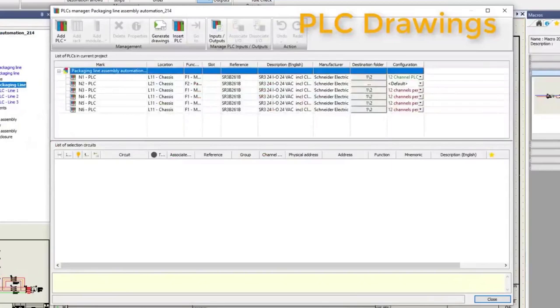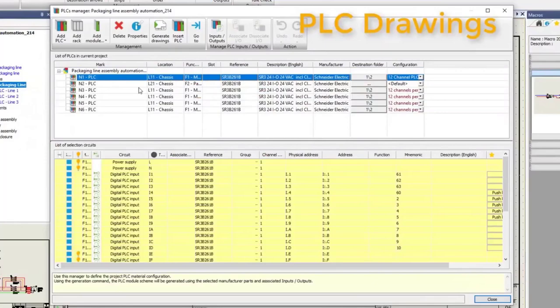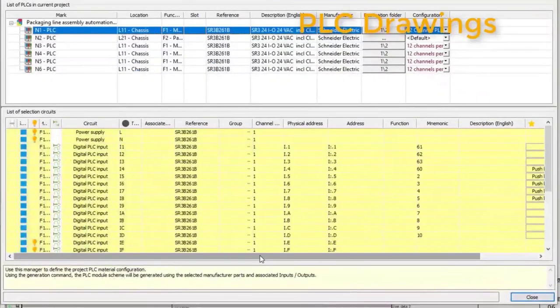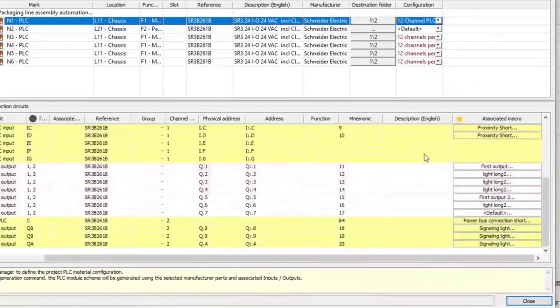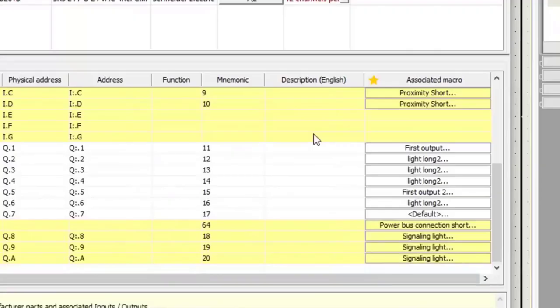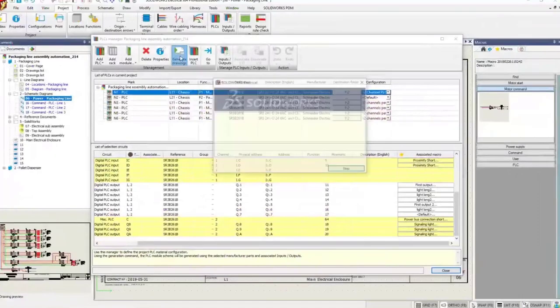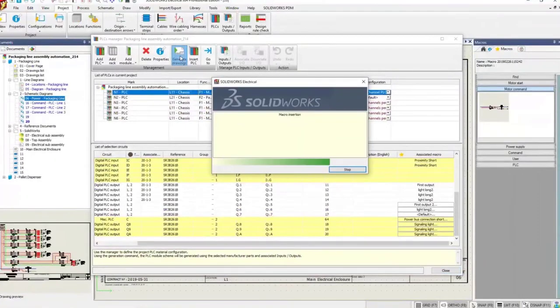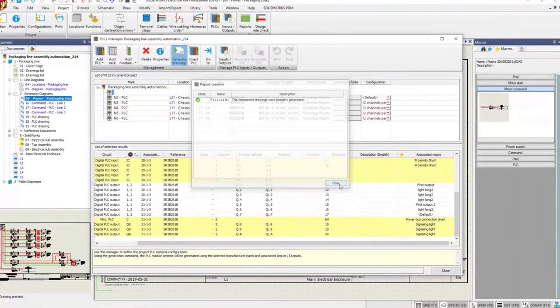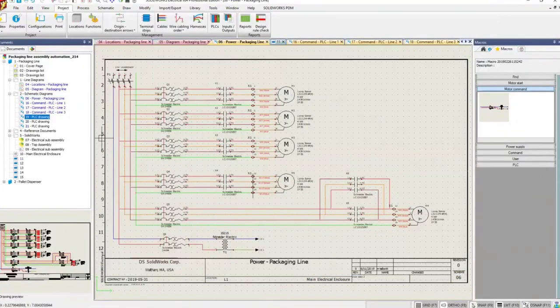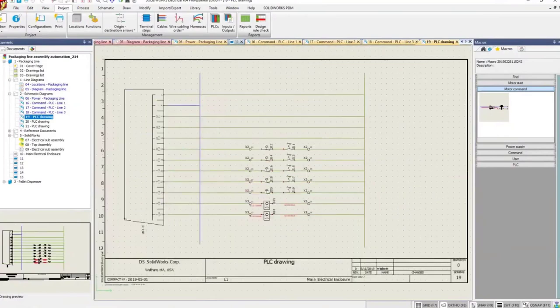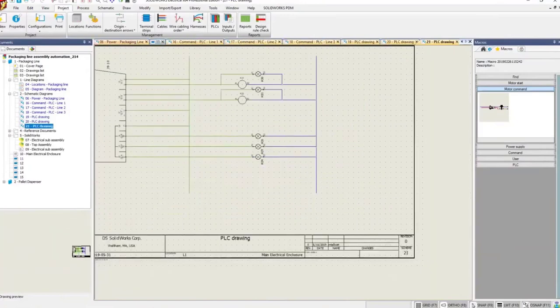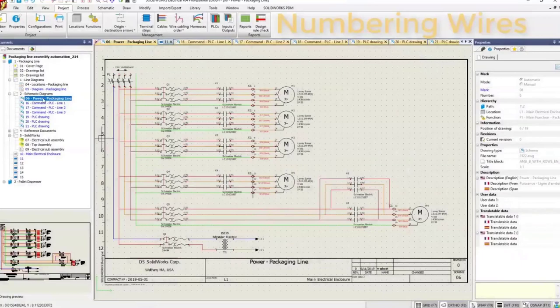Well, that's great that I can insert a PLC all in one go as a library entity. But what if I want variability per channel? In other words, it's drawn with different circuits every time I use it. Well, we have a PLC drawing tool that can be configured and set up. And that allows us to add macros per channel. And those macros can then be generated into drawings. So in other words, I've now configured per channel what is to be drawn from my PLC, and it will spit out the drawings for me. Now I have variability for that specific use case.